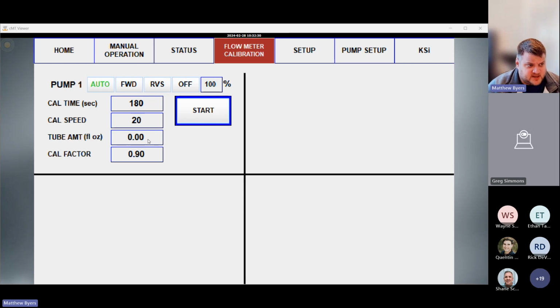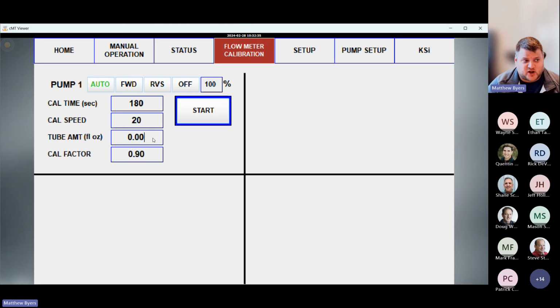Good point, Shane. With this system, and it's not just this box, if you see that cursor flashing like it does on this screen, press enter. This was one of the big things we noticed last year, and it's just the way this touchscreen is designed. Pressing enter on your data is what submits the data. Last year we had a couple people call and say, hey, my cal factor is 0. I've run 2 or 3 calibrations and it's not working. What was happening was they were typing in, say, 58 ounces, and that cursor was just sitting there continuing to flash.